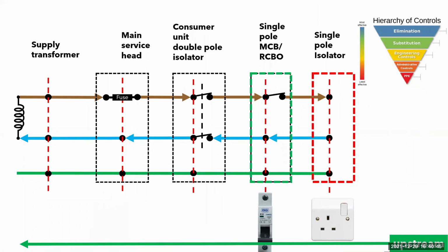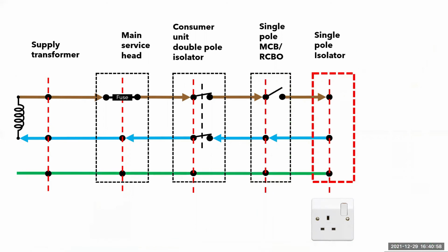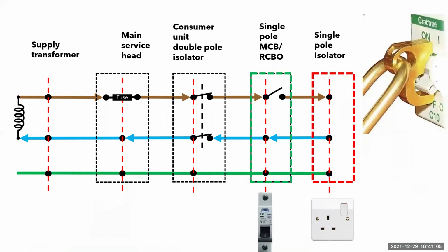So now that we have identified our point of isolation, we need to seek permission to isolate, which is our admin controls. Once this is given, we can now operate the MCB, and we can also secure it in the off position by using a lock-off toggle, like the device shown here. This fulfills the engineering controls and prevents people tampering with your control of the installation.